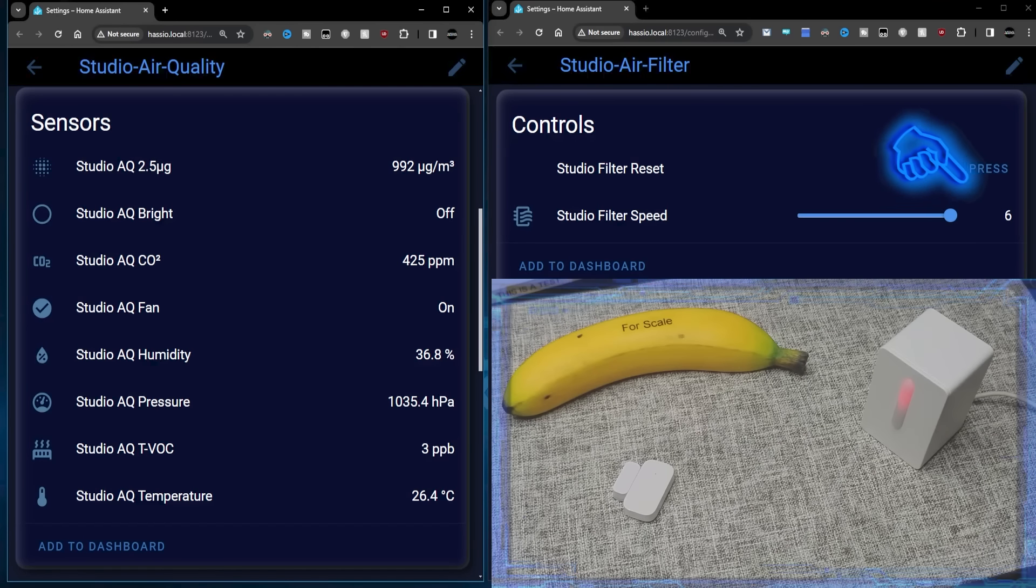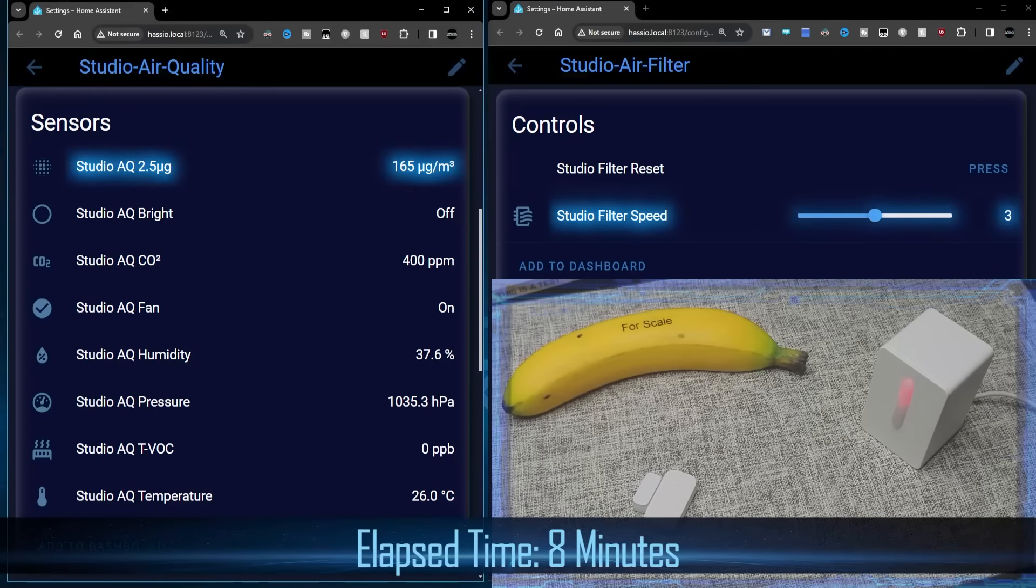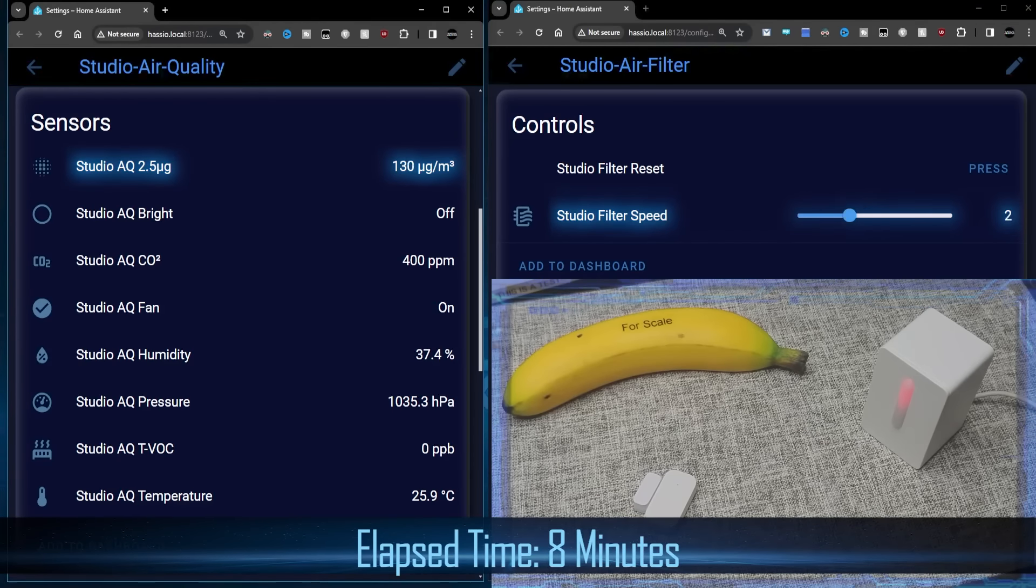Now I'm going to open a window, put a big fan on, just to clear the smoke out of this room. And we can watch the particle count go down as well as the fan speed go down. Another thing we can do, if I mimic the window being open by opening that sensor, you'll see now that the fan's gone off. And if I close the window again, this is my automation trigger. We can see now the fans come back on again.